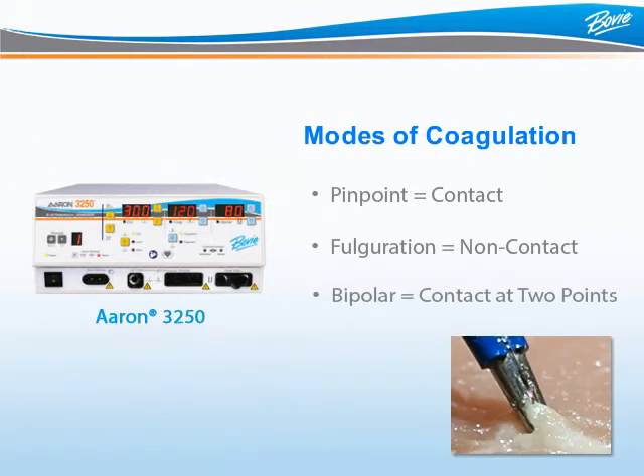In bipolar coagulation, energy is delivered between two points using a bipolar accessory such as bipolar forceps. The doctor uses the forceps to grab the tissue and delivers energy to a specific area. A bipolar foot pedal and bipolar cable are required when using bipolar mode. Bovie offers a generous assortment of optional bipolar forceps for your surgeon.